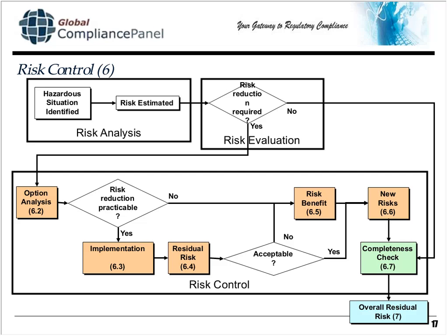If the answer is no, then I'm going to justify the issue here by looking at risk-benefit analysis. In other words, I'm going to ask the question, what is the benefit of this medical device, and does the benefit associated with this hazard outweigh the risk? If the answer is yes, the benefit outweighs the risk, then I'm going to move on.